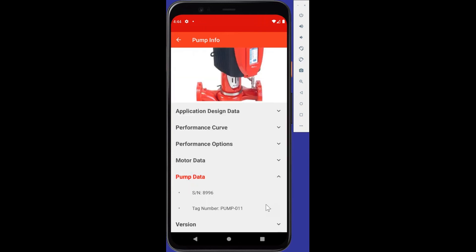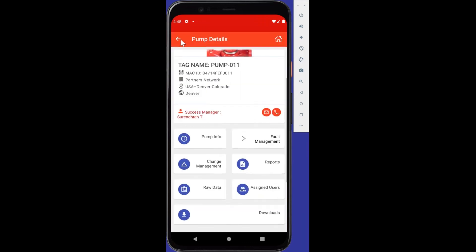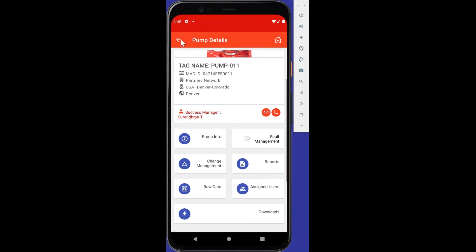If I go ahead and hit the pump data, we'll get the serial number there. That's obviously a simulated serial number. And the tag number, meaning what you define on the DPC touchscreen as the tag. Maybe you called it CHW, chilled water pump one, or you just put P1 or DE11. Whatever you put, that's what we'll see there as the tag number. And then any firmware versions that are on that pump. So this is a simulated pump in Denver, Colorado. It's showing 1.25 with the DPC serial number. Let's back out of that.